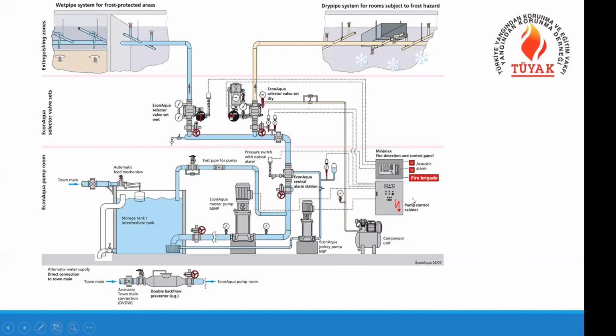And there is a detection and control panel controlling all these systems and seeing all the signals from water flows, the alarms, and it's informing the fire brigade from this panel. Also, we have the pump control cabinets in coordination with the flow switch and pressure switch. It's operating automatically and restarted manually. So it's a general system overview.